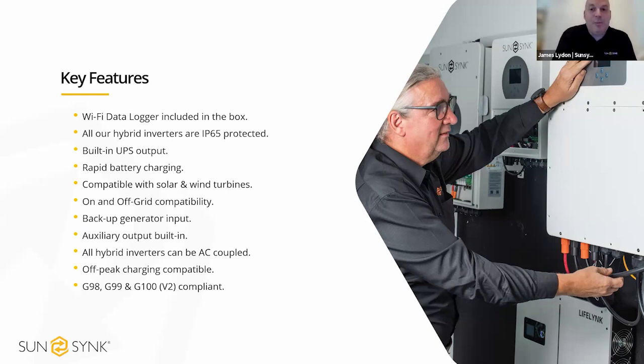We have an auxiliary output built into all of our units. So this is a great feature. And essentially what this does, it works similar to your eddies and your iBoosts. So we've got that dedicated output on the inverter where we can set parameters, or the installer can set parameters for the end user to say, if the system starts exporting to the grid, we can divert that power to a connected immersion heater or some air source heat pumps and any AC source, essentially.